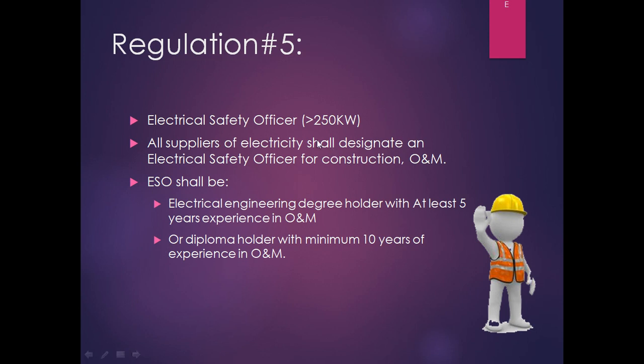There are three things. If the plant load is more than 250 kilowatt, or a supplier of electricity, they have to designate a person as electrical safety officer. Second point, the electrical safety officer's requirement: he should have some educational qualification like an engineering degree or diploma, and secondly, he should have work experience in operation and maintenance.